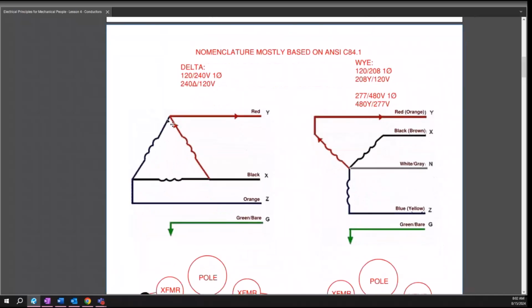Whenever it's single phase, it's normally just a single transformer, you don't have the other two. This is what most residential houses have, just a single transformer up on the pole. The other place I see 240 delta three phase is industrial facilities. A lot of them don't need neutrals, so why install one? 240 is a lot more efficient than 208 when it comes to amperage and conductor loss, since it's just a bunch of motors. So places like oil and gas, industrial parks, a lot of them have just 240 setups.